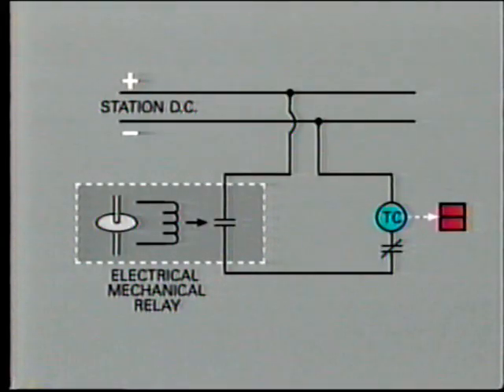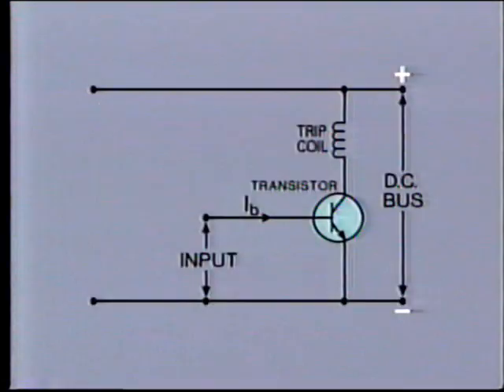In the electromechanical relay, the tripping circuit is energized by closure of contacts, which in turn respond to a magnetic coil. In the static relay, the same result is achieved by some form of gate, such as a transistor. When the signal current achieves a preset level, it effectively opens the gate and current flows through the transistor to activate the tripping circuit. In practice, further amplification and auxiliary relays would be required.